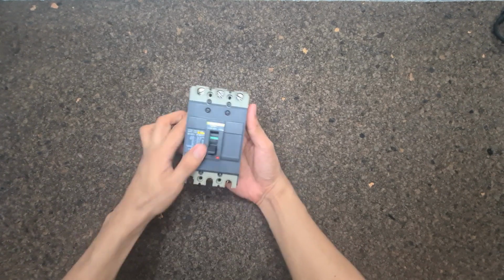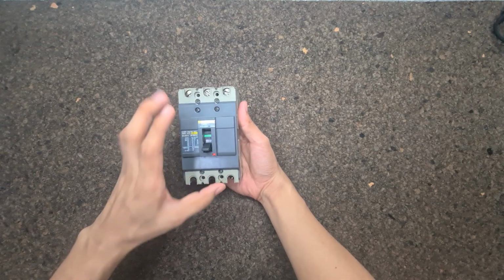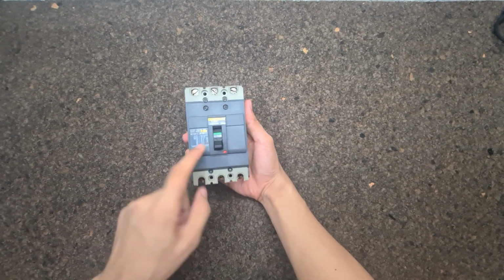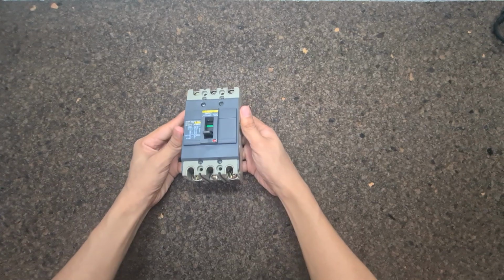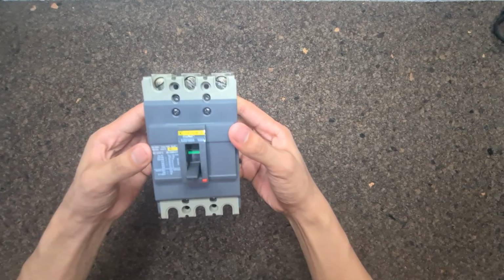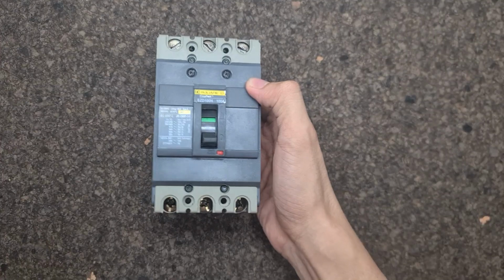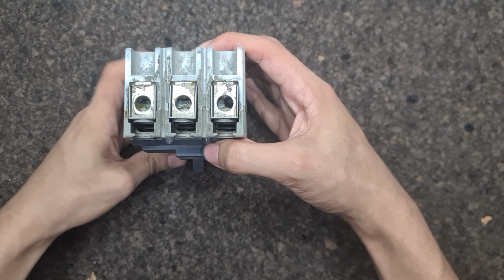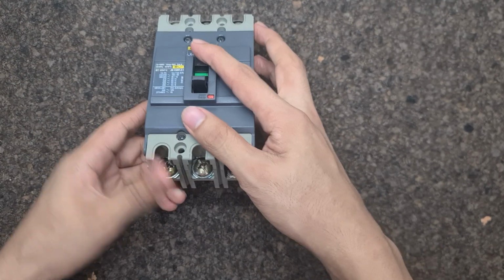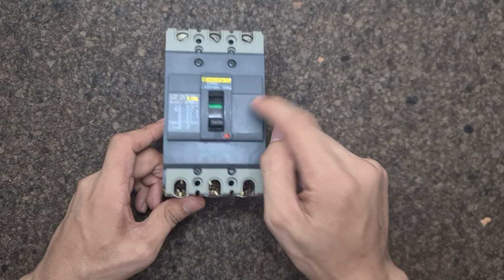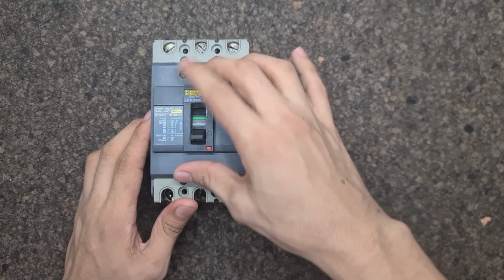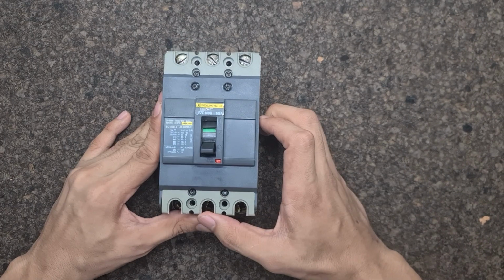I have here a 3-pole circuit breaker, specifically a molded case circuit breaker type, and we will try to open this to examine the inside condition. This circuit breaker encountered a short circuit fault, which is why we will try to find out what happened inside the circuit breaker after encountering this kind of fault.